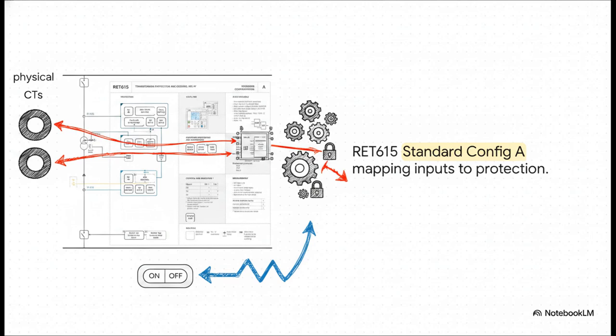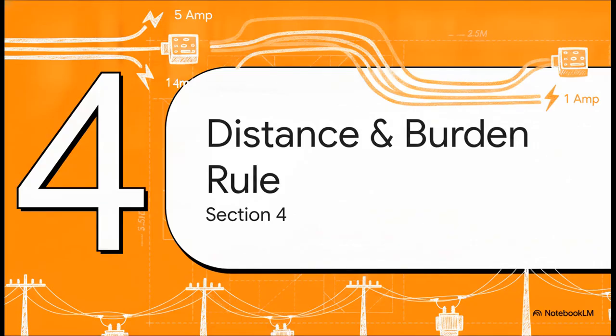The analog signals flow straight from the physical CTs through the properly scaled input ports directly into the relay's internal protection blocks. But think about it. If you get that software toggle wrong, every single downstream protection block is going to inherit a fundamental mathematical error. All right, Part 4, the distance and burden rule.